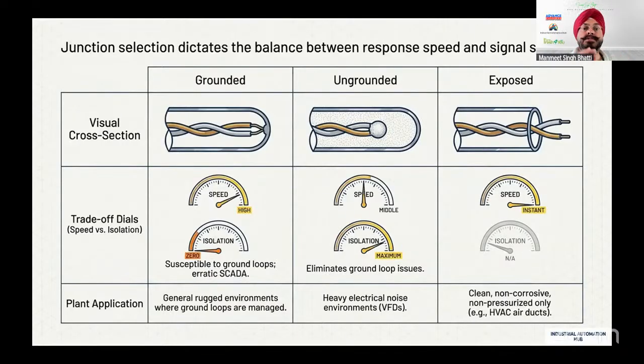It is very prone to installation mistakes. So you should be installing it in a proper way. The grounding should be proper. It should be an instrumentation grounding, not an electrical grounding. No noise should be there. Shielding should be properly grounded. But yes, it's one of the fastest moving thermocouples that can give you an output.